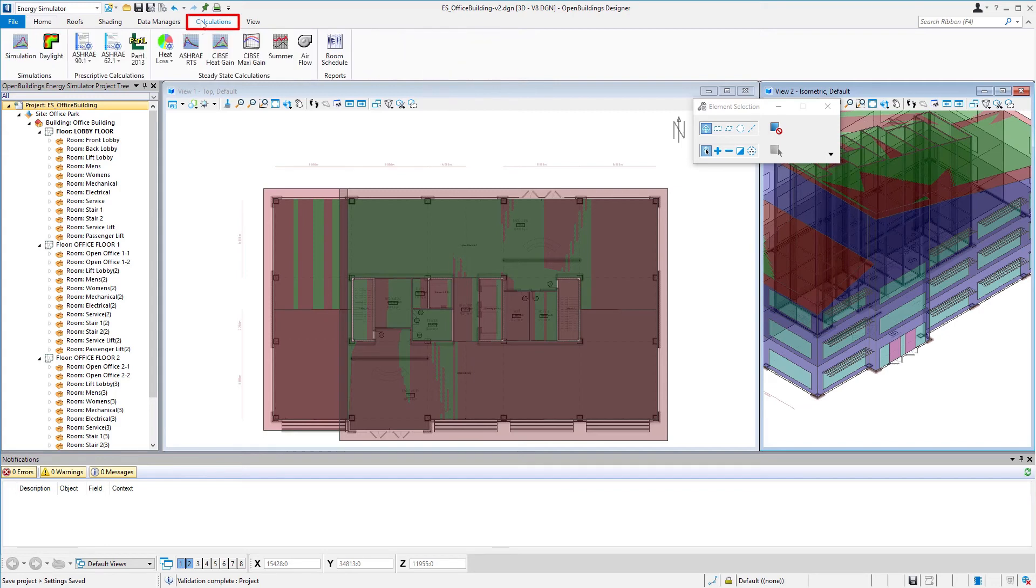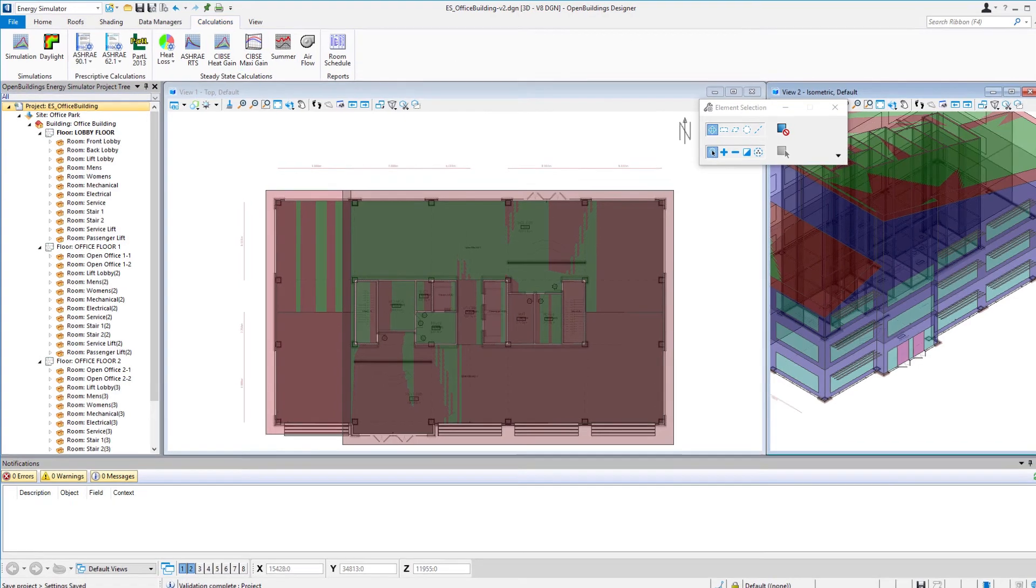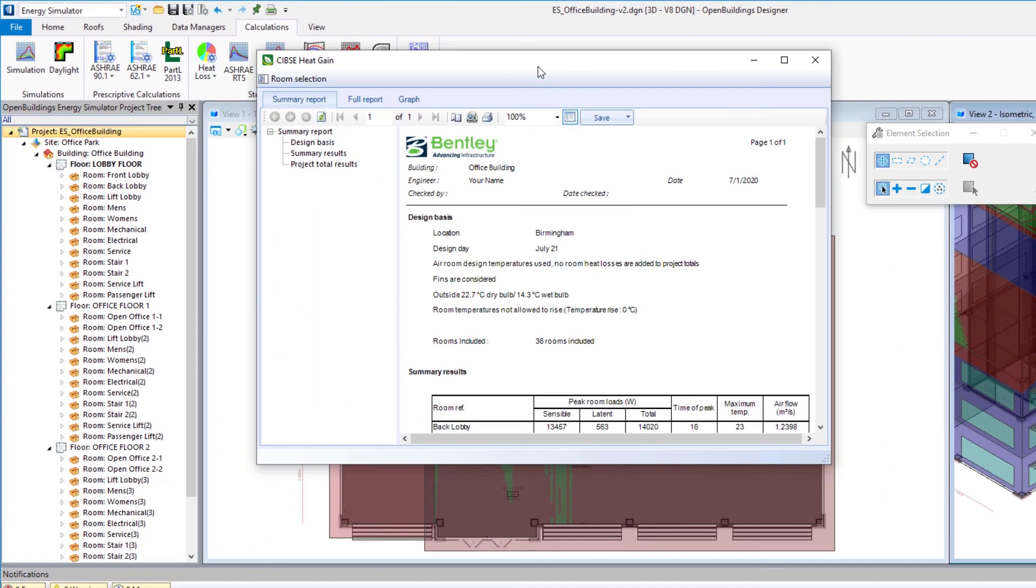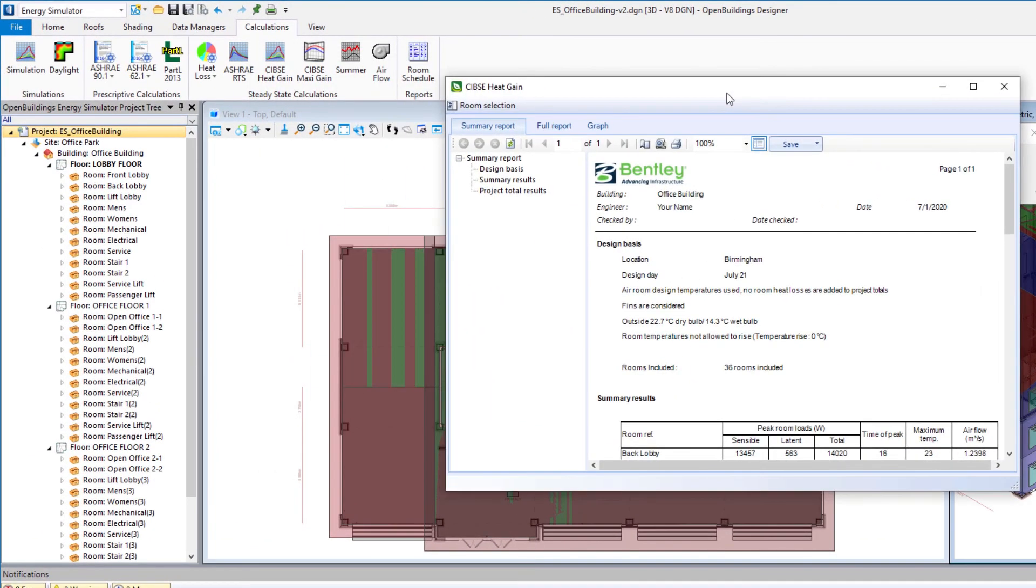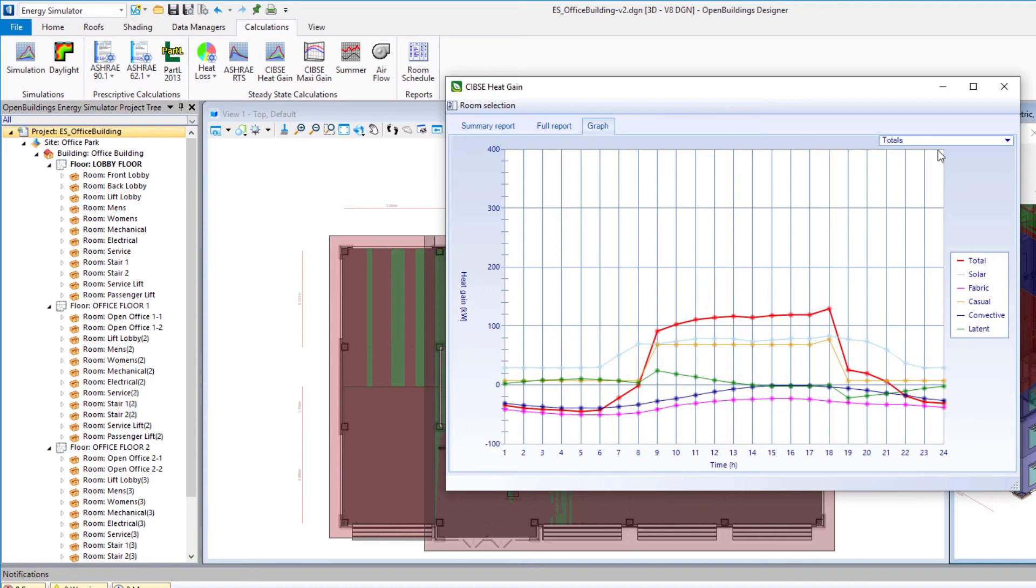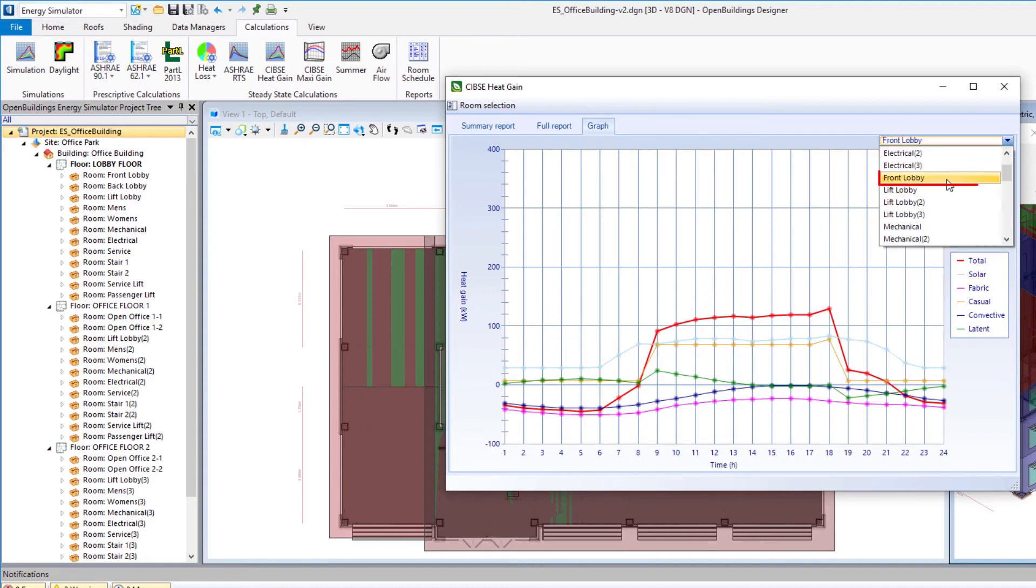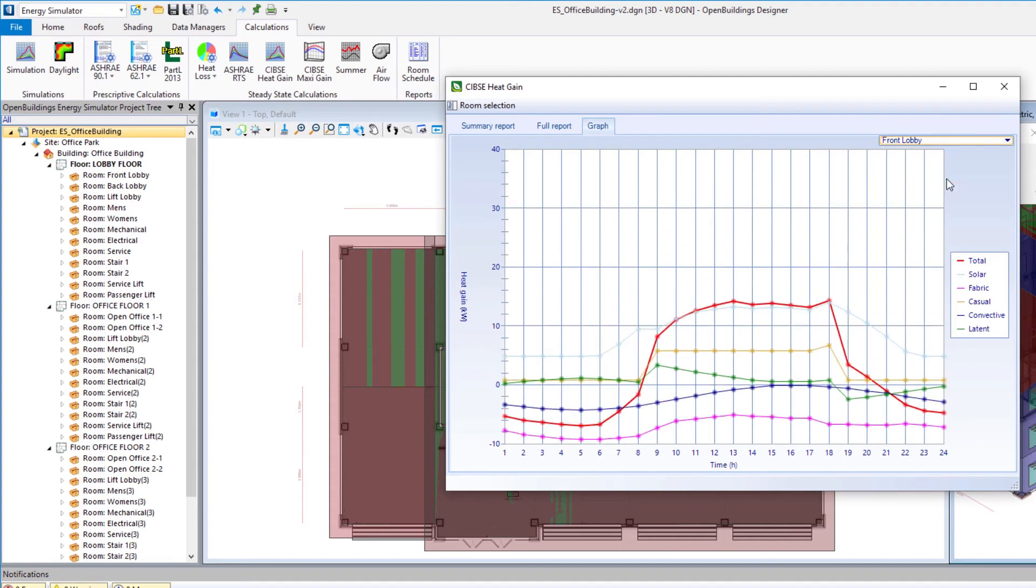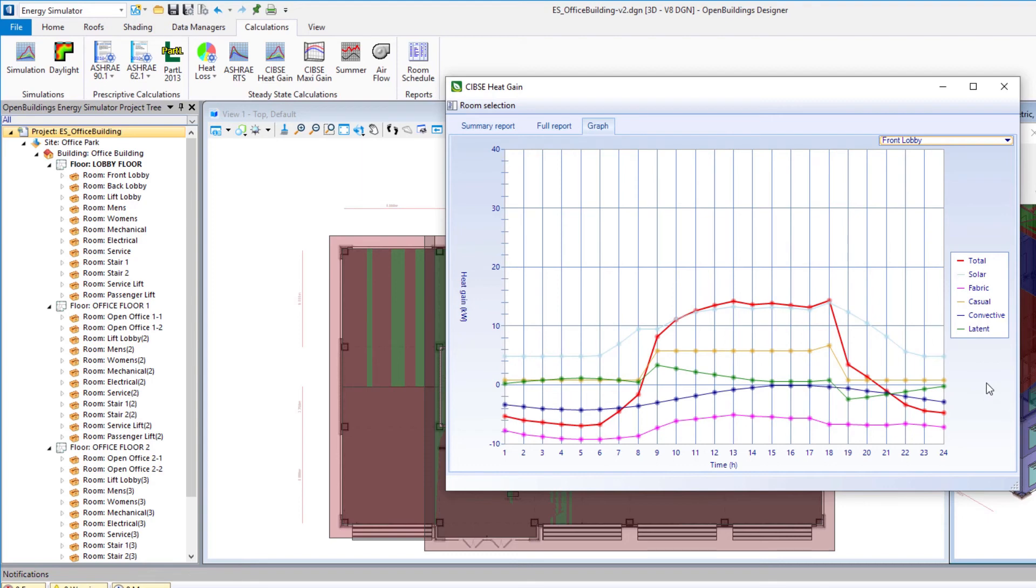And then I'm just going to go back to the calculations tab and select the CIBSE heat gain report again. And just to quickly view that I'm going to go back to the graph. You may notice that our total heat gain from solar has decreased a little bit. And if we specifically go in and look at the front lobby, whereas before we could see that graph was almost up to 20, it has come down somewhat and that would be due to the change we made to the fins.